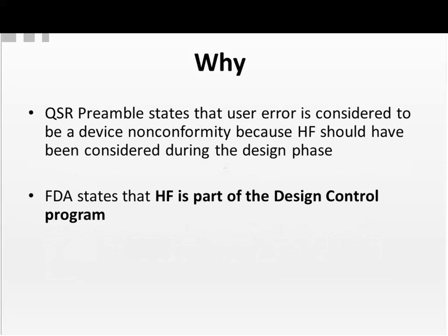The QSR preamble also states that user error is considered to be a device nonconformity, because human factors should have been considered during the design phase. And another important point, that human factors is considered by the FDA to be part of a design control program. You cannot have a complete design control program without considering human factors as part of your design.